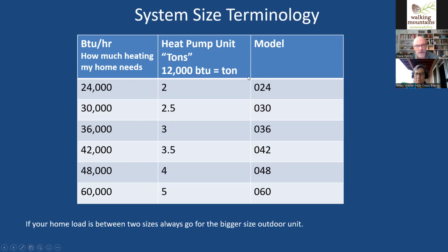A ton is 12,000 BTU per hour, so it might be 48,000 BTUs, a 4-ton unit - that's what they'll say. If you look at the model numbers in their quotes, somewhere in there you'll see numbers like 024, 030, 042, and that way you'll know how much it is, even if they don't explicitly say 4 tons.